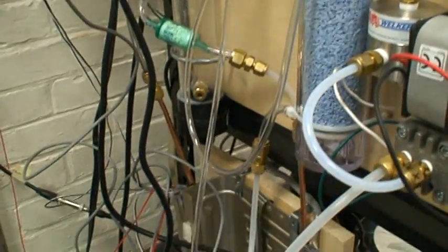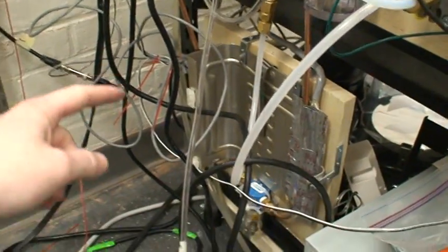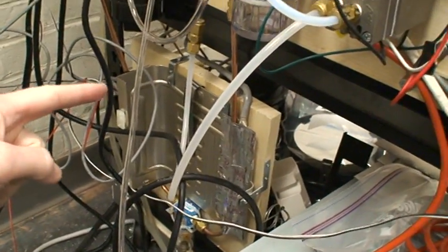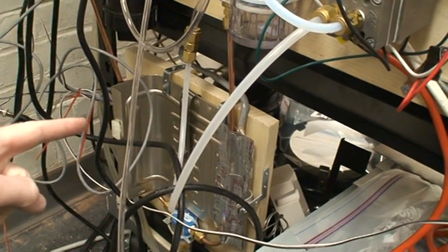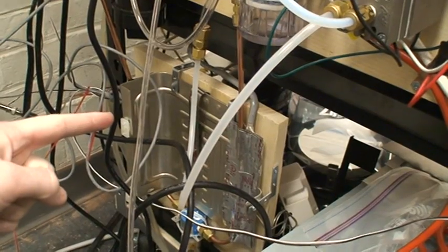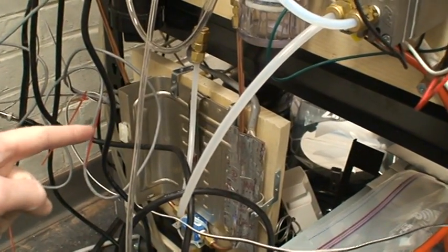right now. So that sampling gas comes out of this connection here, runs down, and then is going to go through a sequence of filters and conditionings. So this is a heat exchanger. It's actually the cooling unit out of a college dorm room size refrigerator, so it works relatively well.